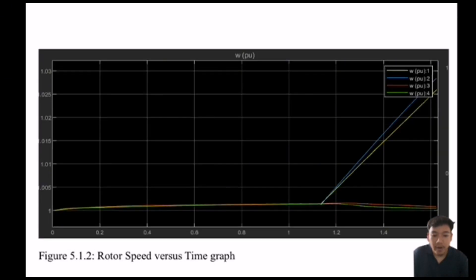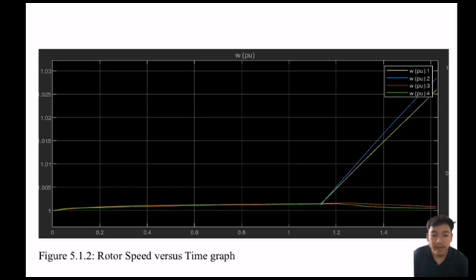For the graph of rotor speed versus time, the yellow and blue lines indicate generator 1 and generator 2 respectively at area 1, while the red and green lines indicate generator 3 and generator 4 at area 2. Before external load is added to the system, the overall generator machines nearly reach the same speed at 100% per unit. However, all generator machine speeds increased significantly and entered unstable condition when the external 150% increment load was added. The generator machine speed of area 1 increased as the incident happened at that particular area and more torque was required to overcome the extra demand.